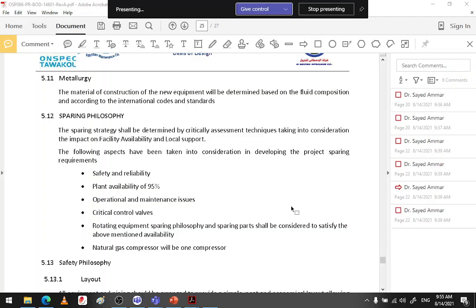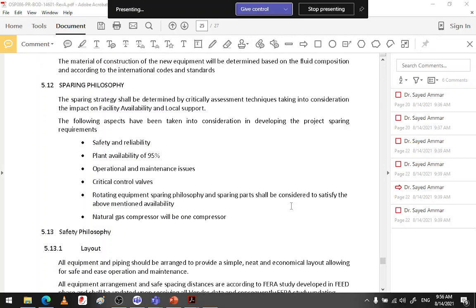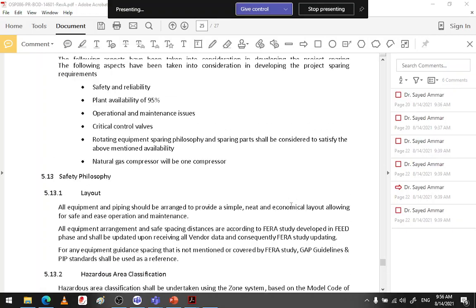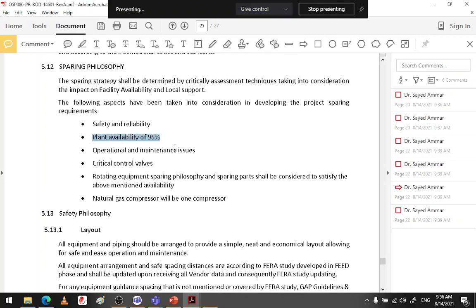That's why we are speaking about the availability. Plant availability of 95% means that 95% of the year's 365 days leaves you almost 18 days to shut down your plant, to make all the necessary turnarounds and maintenance you need to do. The minimum for accepting any plant is 95. Okay, that is for the sparing philosophy. Anything that affects plant availability will have a spare.